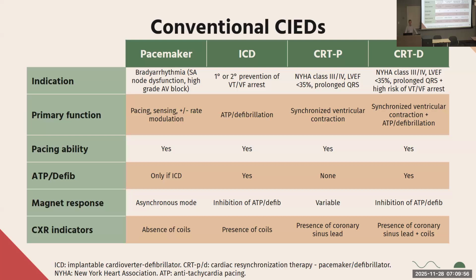All conventional ICDs can pace. And then the magnet response is that it inhibits the anti-tachyarrhythmia therapies, but it does not put the ICD into an asynchronous pacing mode. So to do that, you have to reprogram.